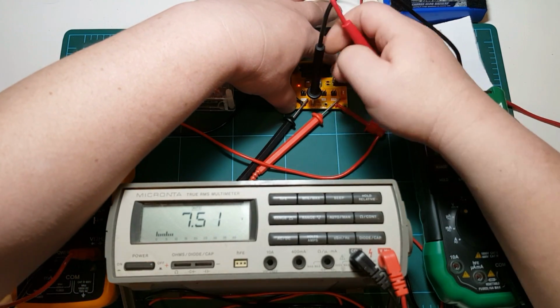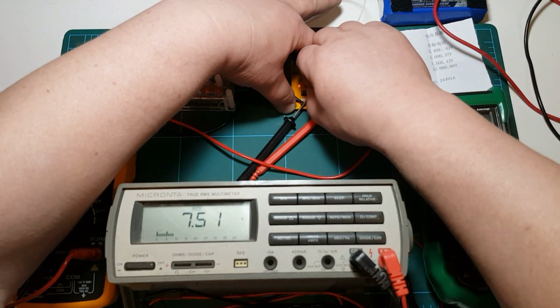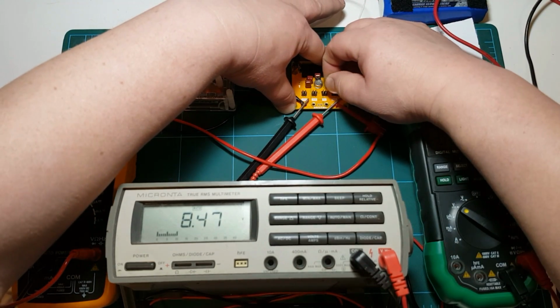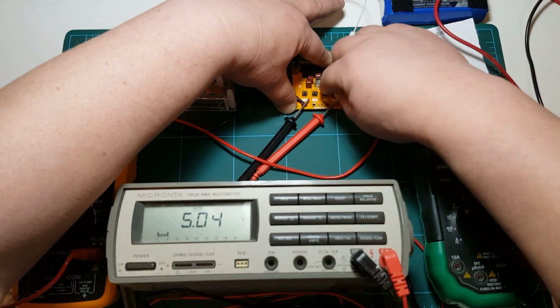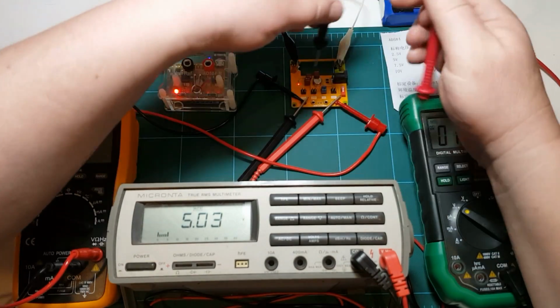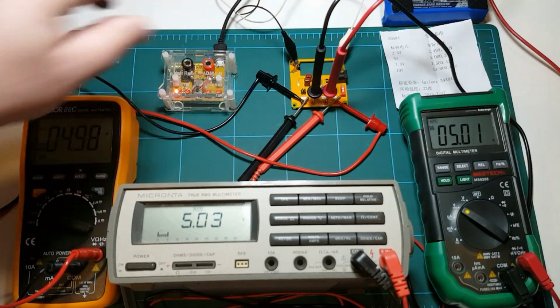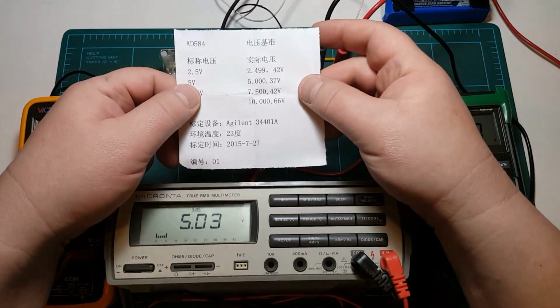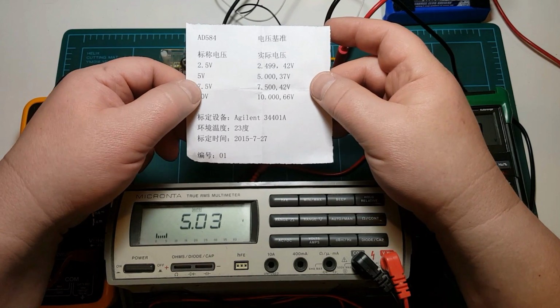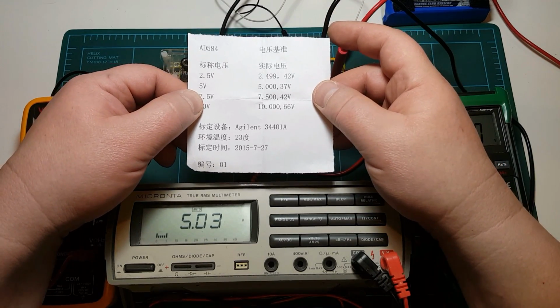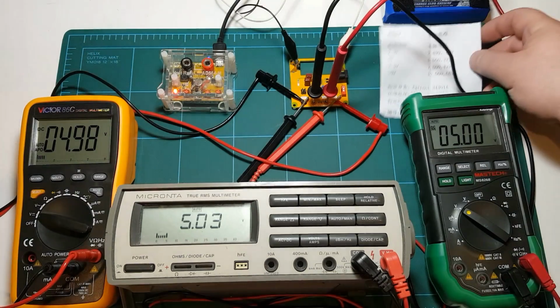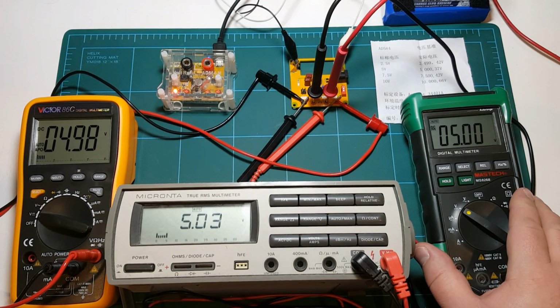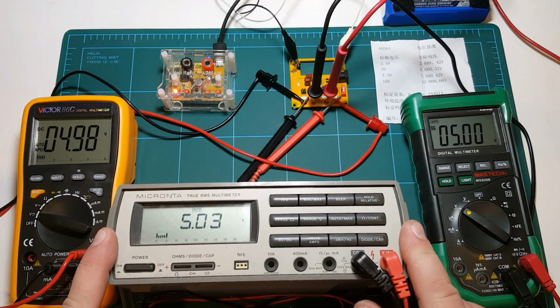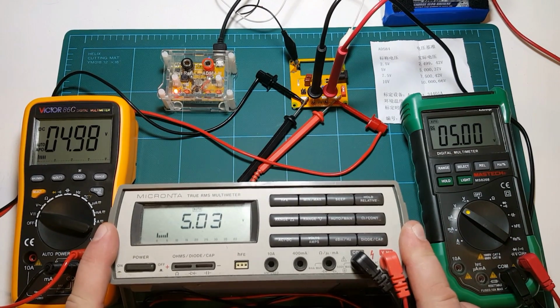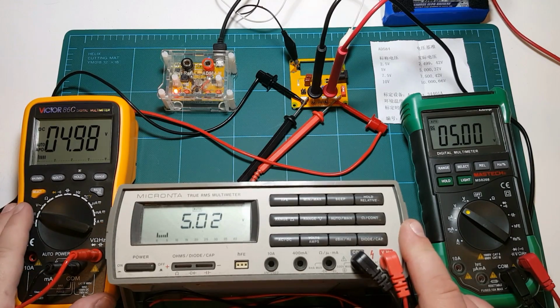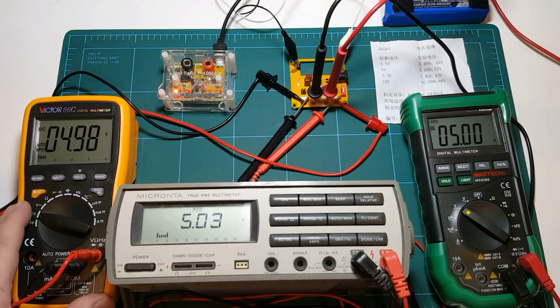That's 7.5 volt, now let's switch to the next range, which is 5 volt. Pop the clips off, move the jumpers, plug in the probe, and let's see what we get. We should be getting a 5.000 reading — the sheet says the board should produce 5.00037 volts. Mastech is spot on, 500. Micronta again is a little on the high side but probably still within spec, 5.03. Victor is a little on the low side but probably still within spec, 4.98 volt.